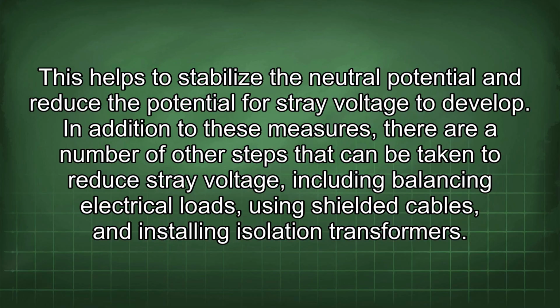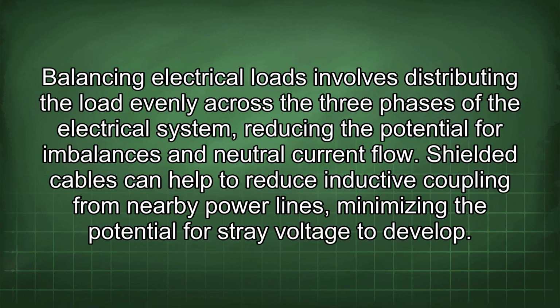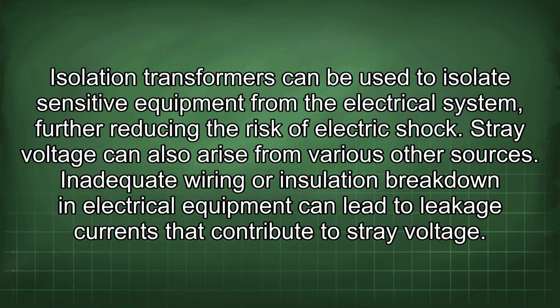In addition to these measures, there are a number of other steps that can be taken to reduce stray voltage, including balancing electrical loads, using shielded cables, and installing isolation transformers. Balancing electrical loads involves distributing the load evenly across the three phases of the electrical system, reducing the potential for imbalances and neutral current flow. Shielded cables can help to reduce inductive coupling from nearby power lines, minimizing the potential for stray voltage to develop. Isolation transformers can be used to isolate sensitive equipment from the electrical system, further reducing the risk of electric shock.